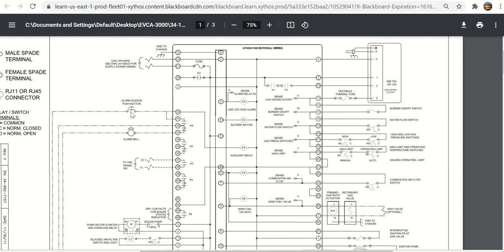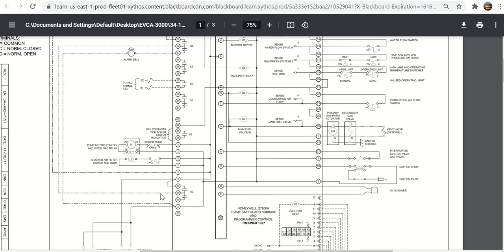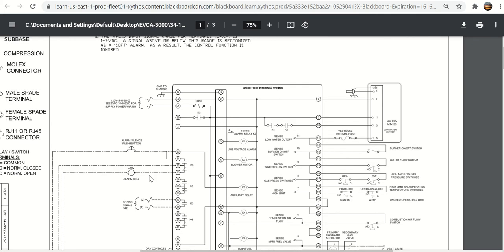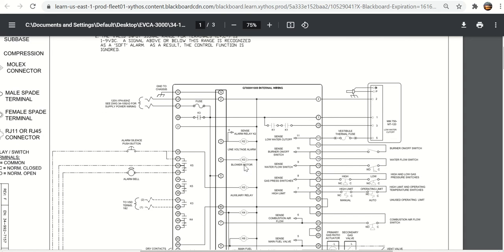If you want to silence the alarm bell, you can press this silence button. It puts power on relay K5, which is called an auxiliary relay. When it does, this contact here closes. Here's the relay that tells or is supposed to enunciate that there's an alarm condition. The flame safeguard has failed for some reason because of a flame failure or some type of failure.